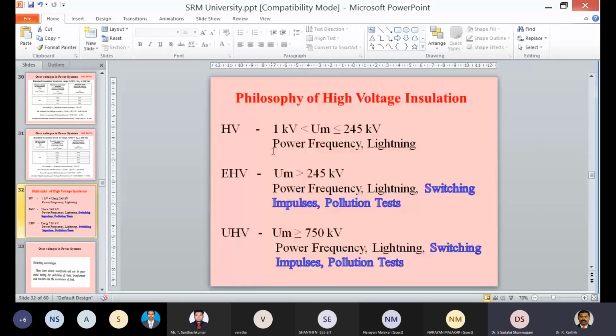Fine, sir. So I have covered only the high voltage part. Now I am moving to extra high voltage, that is, when the system voltage is more than 245 kV. Under extra high voltage, your switching transient also comes into the picture, along with the power frequency and the lightning transient. And a pollution test I will cover at the end: why it is important and how it affected the Indian system in recent times.